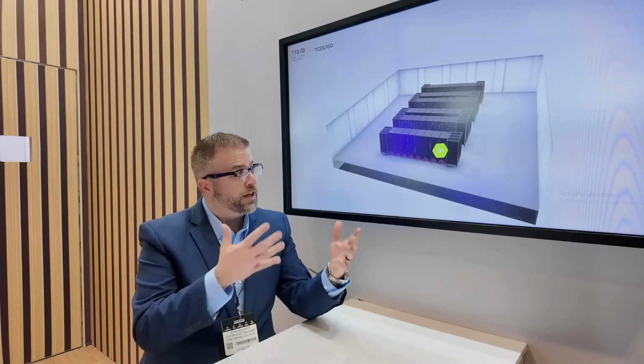But looking within the TCDU, what we have come up with, this is our TCDU 150, we can actually navigate to the performance specifications here. But with the TCDU 150, what makes that unique? We are targeting a sweet spot at approximately 1 to 2 bar, anywhere from 200 liters per minute up to 300 liters per minute. Specifically, the TCDU 150's sweet spot is 225 liters per minute flow at 1.8 bar. The other unique thing about this is we are able to do that within a 4U rack size. So we're trying to maximize output while minimizing space claim.